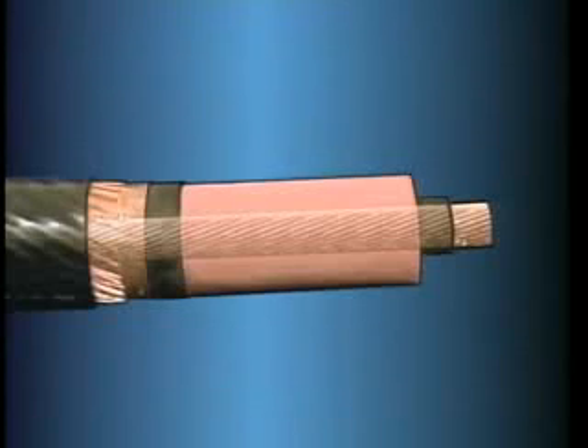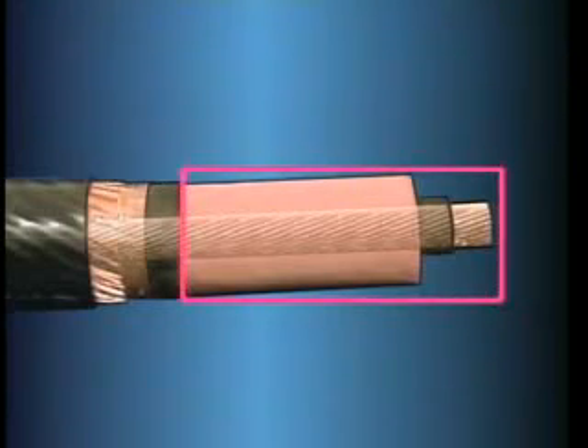To maintain the necessary separation between the conductor and the shields, a portion of both shields is cut back from the end of the cable and removed. As shown in this side view, the insulation shield, the metallic shield tape, and the concentric wires have been layered back from the insulation to separate them from the conductor. When this is done, however, there is no voltage stress control beyond the shields.